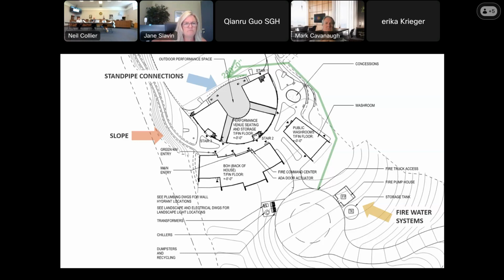Is there a fire alarm system or occupant notification system? Yes, we'll have all the normal visible and audible fire alarms. We'll have smoke detection in the enclosed spaces, and under the shade structure we'd have some version of heat detection. Smoke detectors won't do well out there, but there will be a heat detector type solution, mainly for off-season fire department response reasons more so than for evacuation purposes.